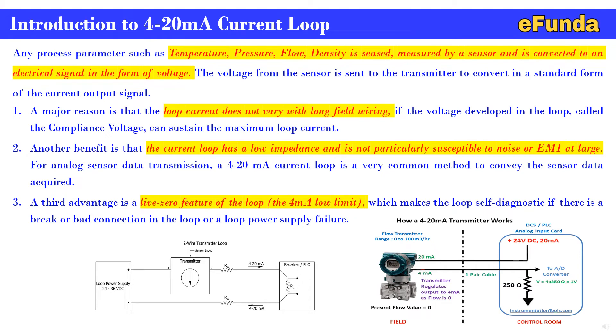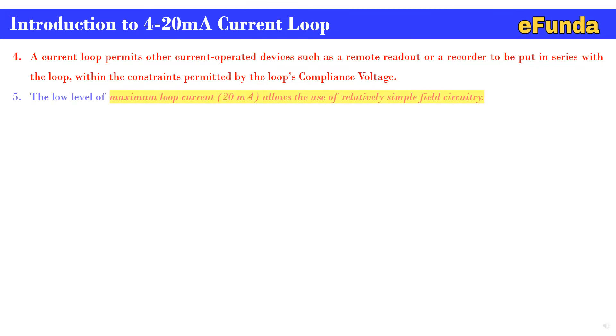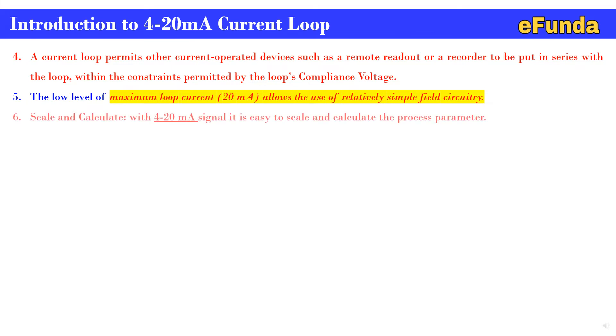Fourth, a current loop permits other current-operated devices such as a remote readout or recorder to be placed in series within the constraint permitted by the loop compliance voltage. Fifth, the low maximum loop current of 20 milliamp allows the use of relatively simple field circuitry. Sixth, it is easy to scale and calculate the process parameter with a 4 to 20 milliamp signal.